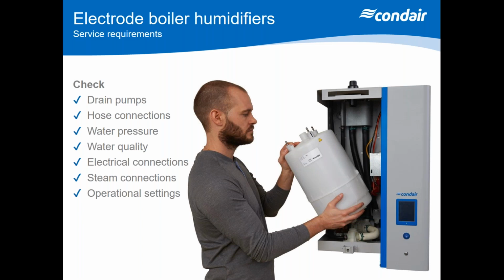So that's another one to consider. Electrical connections, always worth tightening up the connections, the big power connections on the contactors, on the solid state relays, and also making sure the caps are tight as well, because they become loose and they're going to create a high resistive joint. So that's always worth checking.